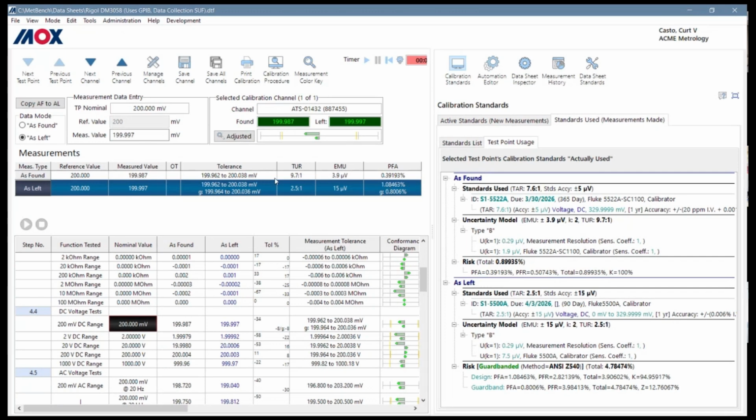Okay, now what's important about this is that MPS then automatically guard banded, and guard banding is optional in MPS. So if you don't want any guard banding, you can basically turn off guard banding. And if you do want guard banding, MPS supports 3 methods for guard banding. It supports the old RP10. If you're familiar with MET/CAL, for instance, it used the RP10, which is just a fixed percentage of the EMU will be the guard band amount.